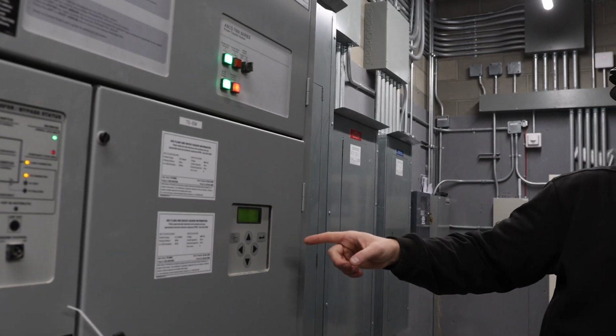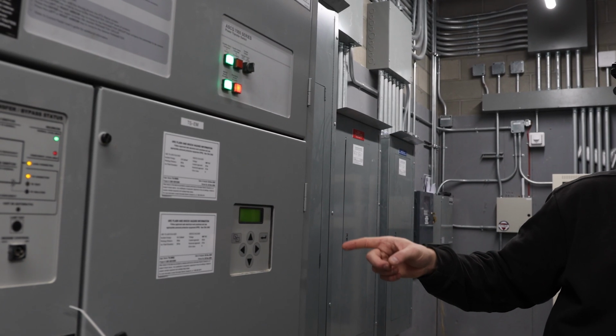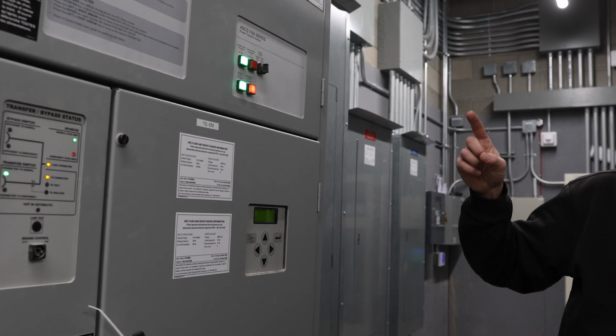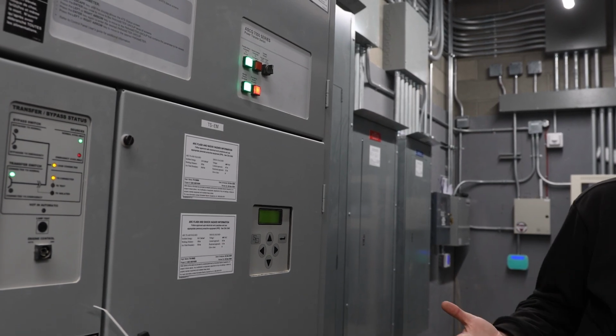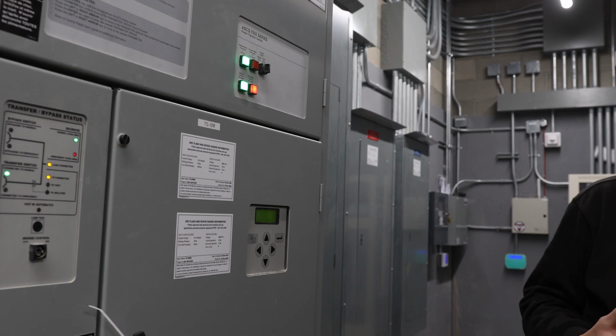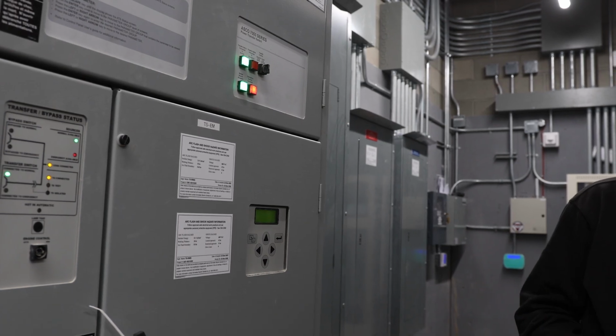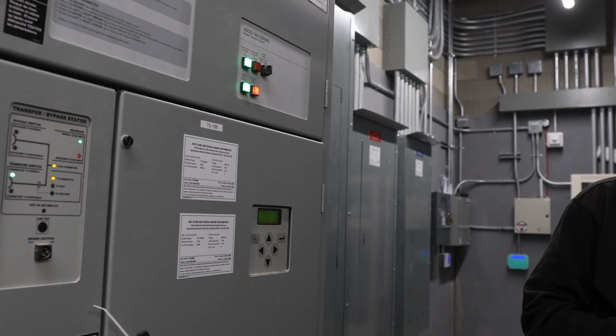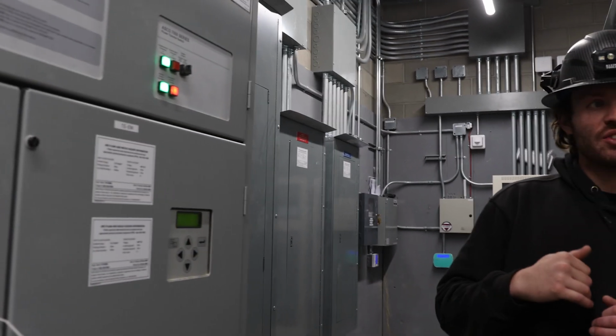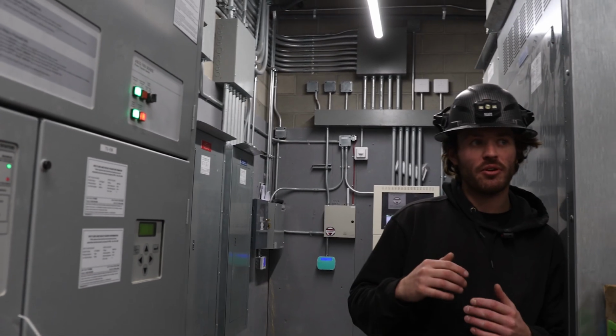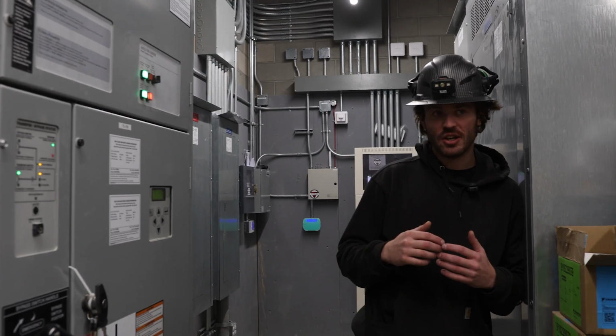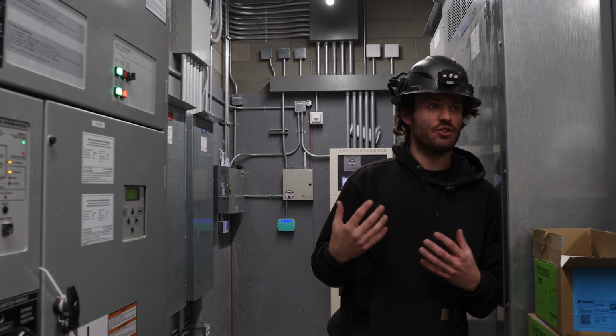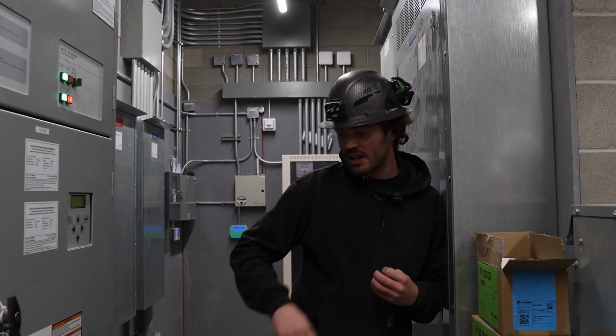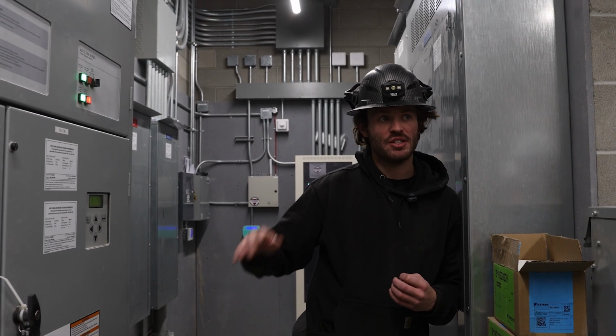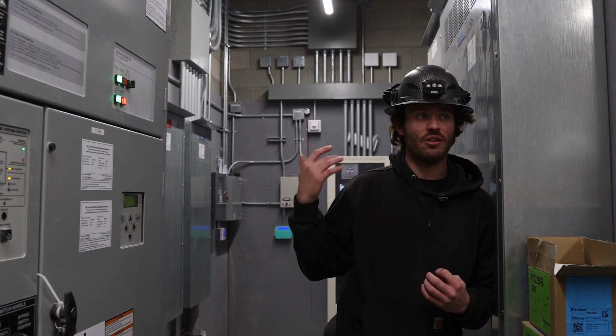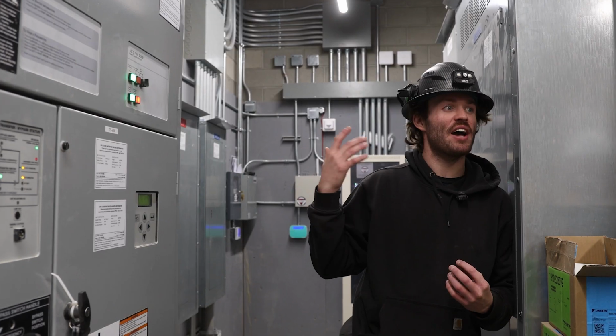The first thing it'll do is a time delay pre-transfer. That signal is going out to the elevator to let it know that emergency power, or a transfer, is about to happen. It'll then do an in-phase transfer. In phase, we're looking for our sine waves, with our voltage and frequency, to be as close as possible. It makes as seamless a transition as possible, lessens wear on the actual mechanism, and when it transfers, it's a lot less drastic.